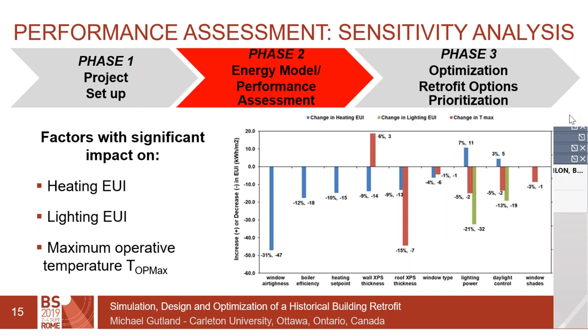An adaptive thermal comfort model was used, which states that when outdoor temperature is higher, occupants are willing to tolerate a higher indoor operative temperature. Before designing an optimized retrofit model, we performed a one-factor-at-a-time sensitivity analysis to determine which model parameters had the greatest impact. Parameters included those related to the mechanical system, window construction, thermal insulation, and lighting. The impact on heating loads, lighting loads, and peak temperature inside the building was measured for each parameter change.